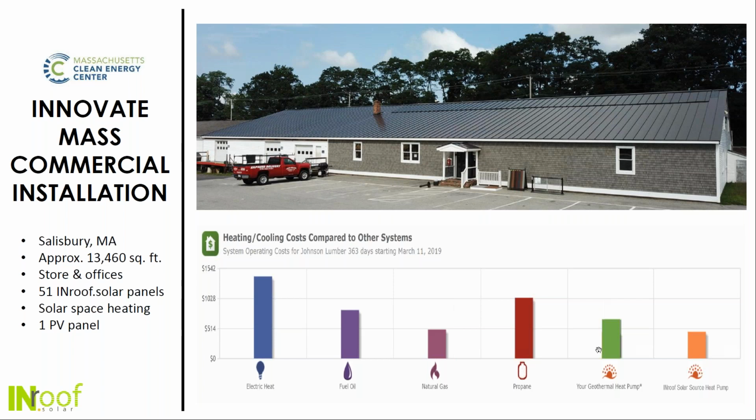So heat pumps can operate very efficiently at 60 degrees Fahrenheit or lower. And in the wintertime, that's not that hard to achieve compared to trying to get, say, 120 for domestic water. We don't have to get nearly that hot with systems like this. So we can operate at low temperatures very efficiently.